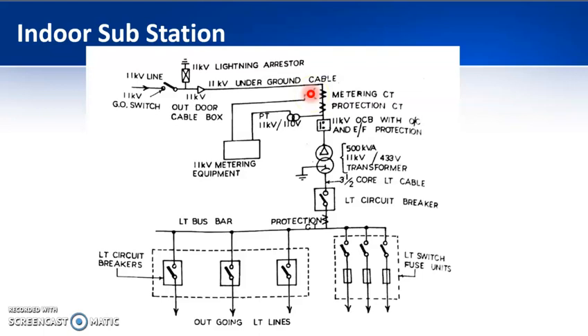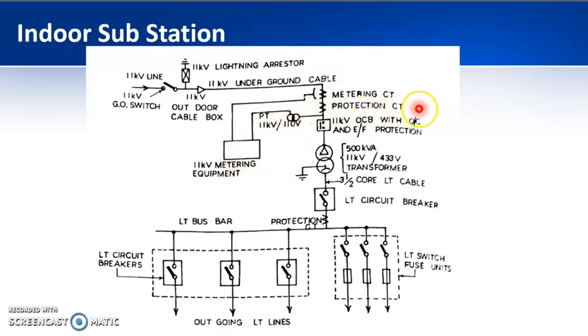A metering CT and a PT are also required — a potential transformer and a current transformer. The metering CT is shown here. For the potential transformer, this 11 kV supply is stepped down to 110 volts using a transformer and then given to a metering equipment. The system also houses a protection CT in order to protect against any kind of faults.